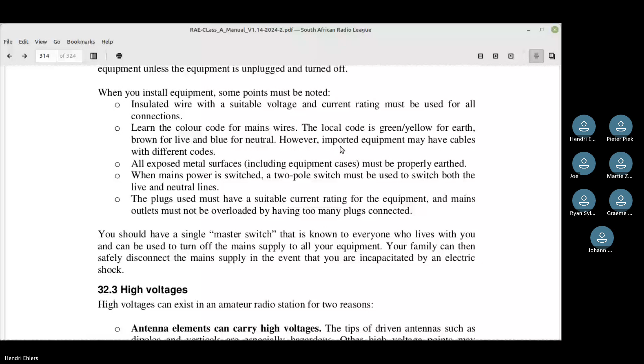Other thing is your earth leakage. How it works is it measures the amount of current coming in compared to the amount of current going out. If there's an imbalance in the circuit breaker or in the earth leakage, it will trip. But it's important that the power does not go through you and back through the other cable. It's important that that item's been earthed. So the yellow, or yellow and green, or green wire is always earth. And it's important to have your equipment earthed.